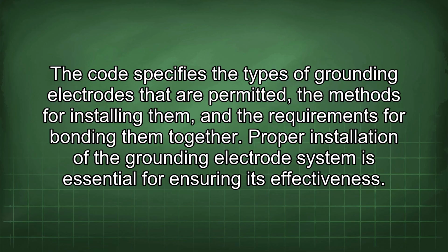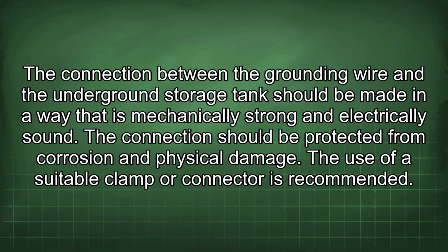Proper installation of the grounding electrode system is essential for ensuring its effectiveness. The connection between the grounding wire and the underground storage tank should be made in a way that is mechanically strong and electrically sound. The connection should be protected from corrosion and physical damage. The use of a suitable clamp or connector is recommended.